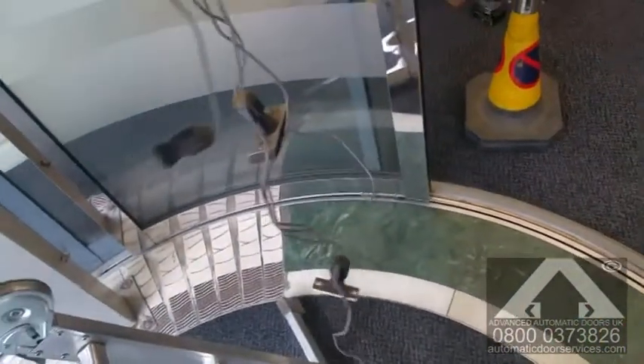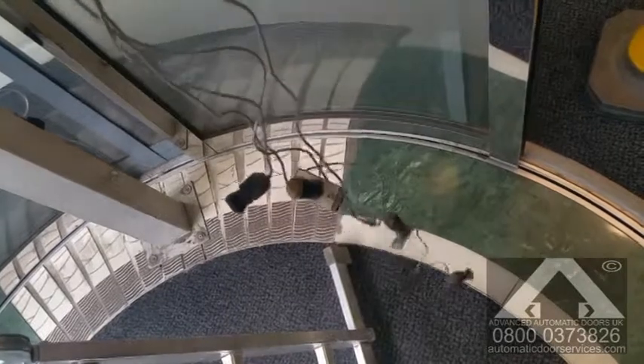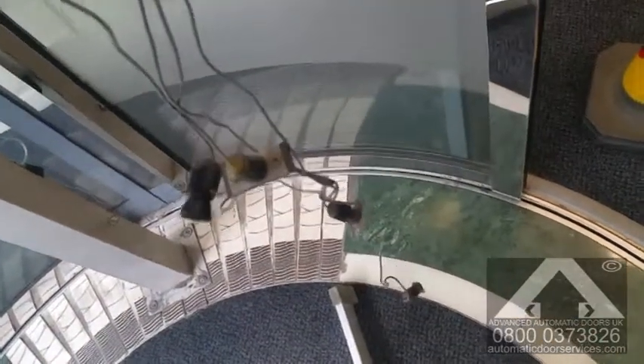Upon further investigation, these are the previous ultrasonic sensors that were fitted on the previous operating materials. The door has since had something called a retro kit fitted, where they strip out the old operating materials and replace them. But even though this was supposed to be an upgrade in safety, this has been a downgrade, as these current internal and external doors have no presence sensors covering the travel area of the doors or in front of the doors. So it's wrong to just leave these old cables up in the ceiling, floating around unnecessarily, creating confusion for fault diagnosis in the future.